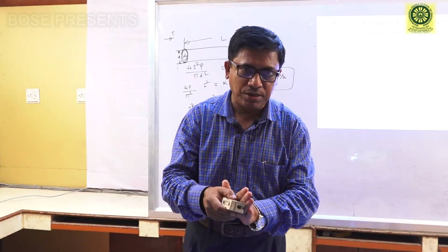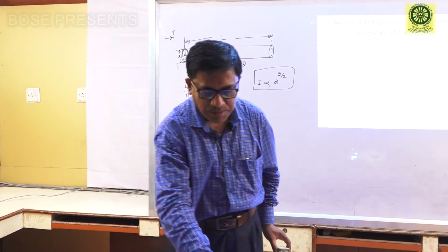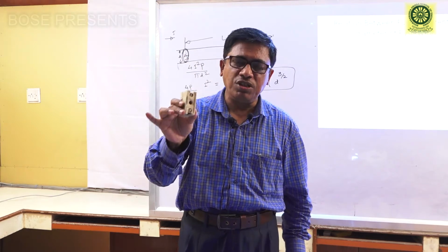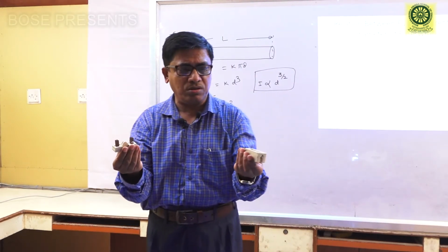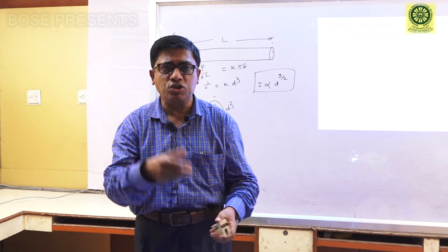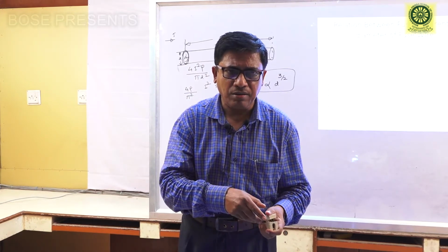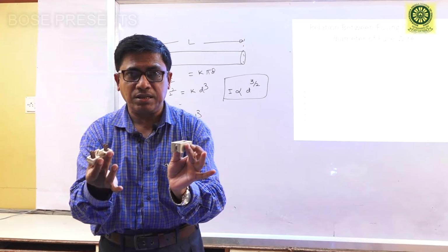Above these fuses, we use the HRC type of fuse, because this fuse has some problems. This is a semi-enclosed type of fuse. It is not completely closed. So what will happen when current flows due to a short circuit or due to a high value of current? Now there will be an arc. It is dangerous. Due to the arcing, it may catch fire. For example, I will show you.